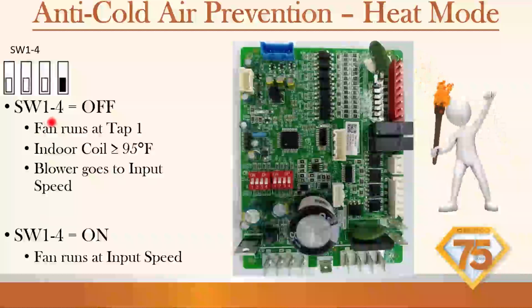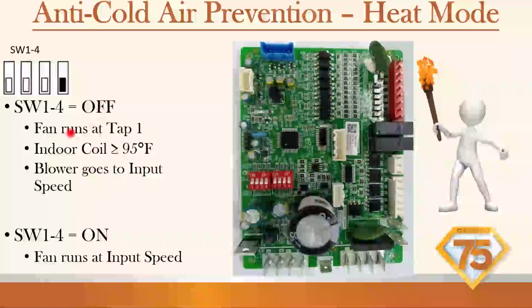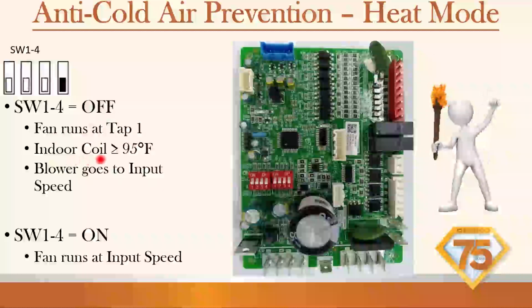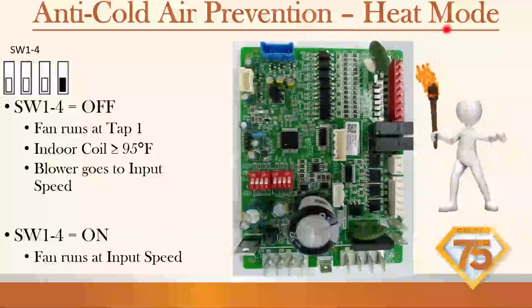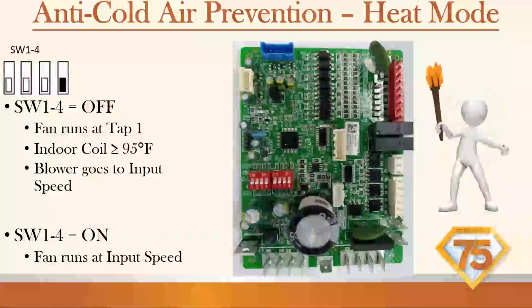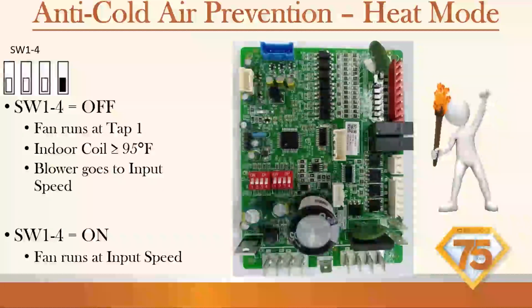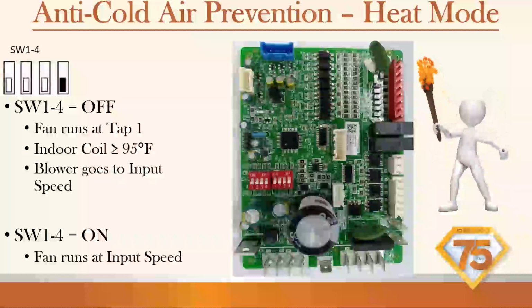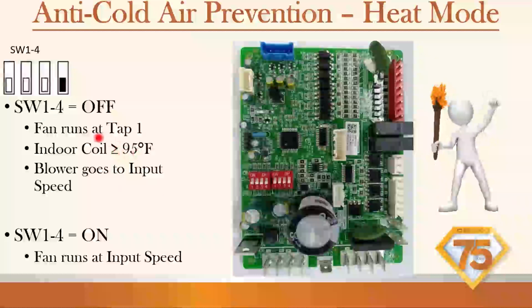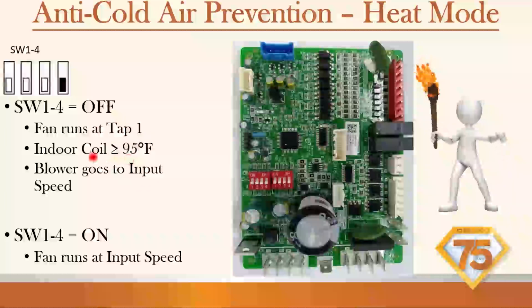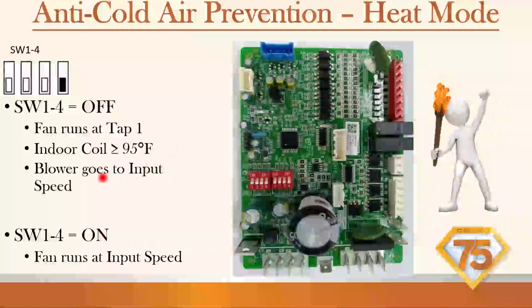But switch 1 through 4 is off. The fan runs at tap 1, indoor coil. So this is the anti-cold air prevention in heat mode. If we just started up the fan right away, as soon as we get a call for heat, we're going to get a blast of cold air for a little bit before that indoor coil warms up. This is saying it's going to hesitate on that lower fan to come on until that indoor coil temperature reaches 95 degrees.